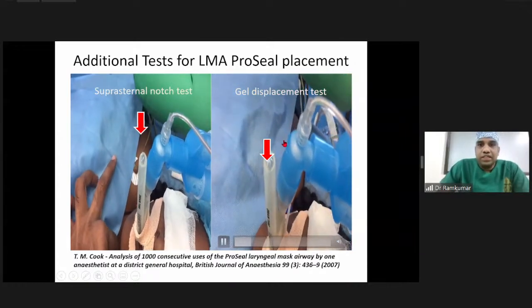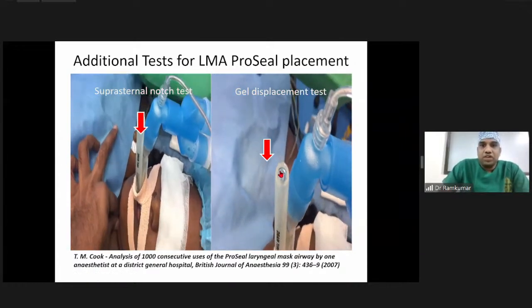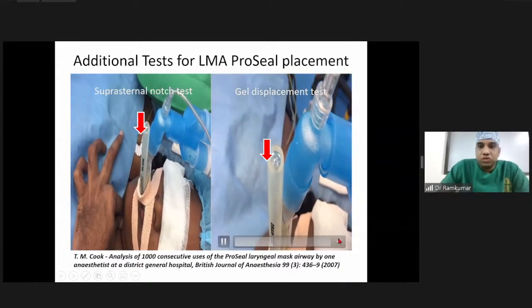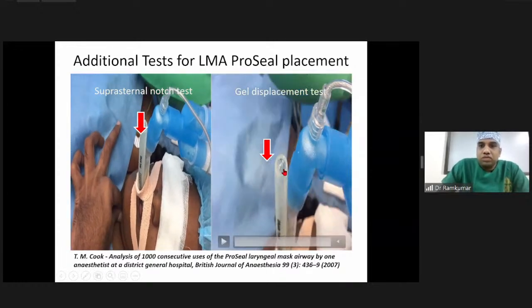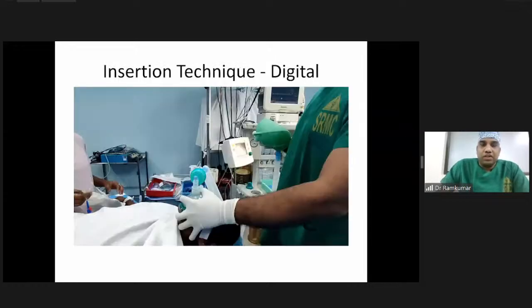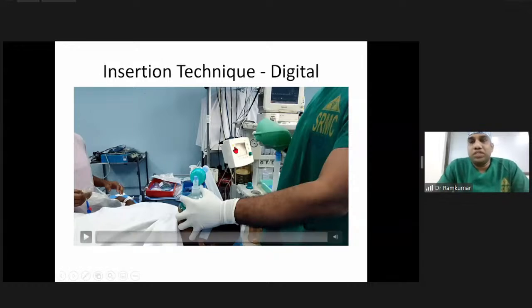Here, the gel displacement test is done with ventilation. You just continue to ventilate, and along with the ventilation the gel has to move up and down like a meniscus. If it is not moving or it is popped off, that means your device is not placed properly, it's too high or into the glottis. This is one of the tests to identify the correct placement of the supraglottic ProSeal. Based on these tests, you can identify whether the placement of your device is correct.